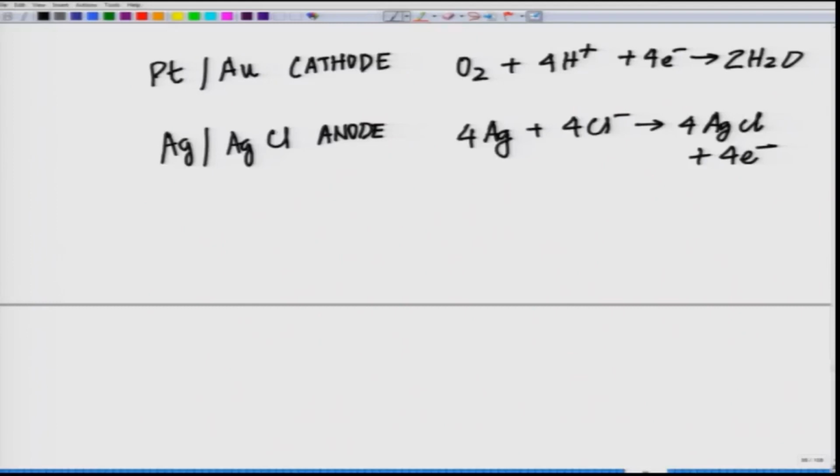The electrode also contains a silver guard electrode extending most of the way to the bottom. The guard electrode is kept at negative potential, so that any oxygen diffusing in from the top of the electrode is reduced and does not interfere with the measurement of oxygen diffusing through the silicone membrane at the bottom. Similar electrodes have been formulated for detection of NO, which is another biological component, hydrogen sulfide and carbon monoxide.